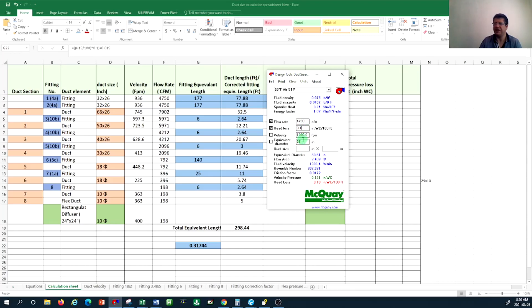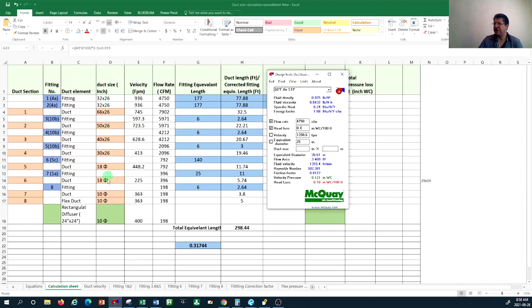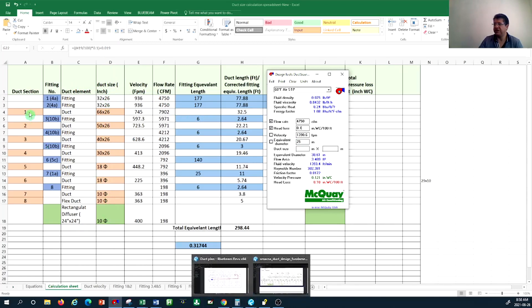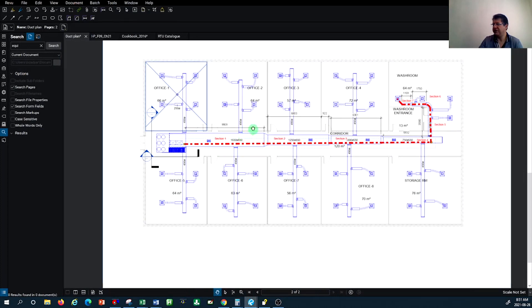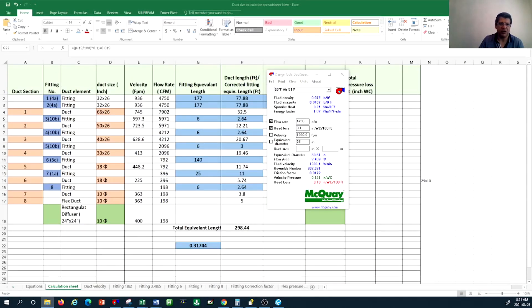The velocity of air is 1,390.6 — fairly high — but in the equal friction method you ignore this effect and size everything regardless of velocity. My other velocities are all lower. In the equal friction approach we ignore the velocity effect in the calculation sheet. You size your duct work and plug in the duct size in the diameter column. I have eight sections highlighted, and I'd like to show you how we do the fitting calculations.